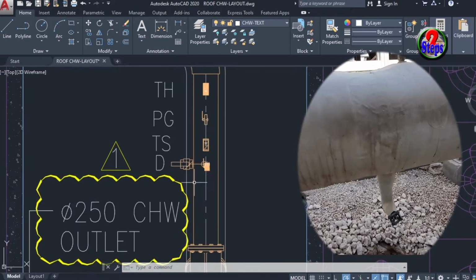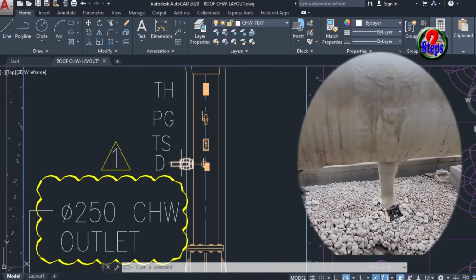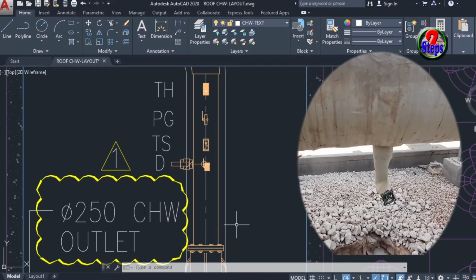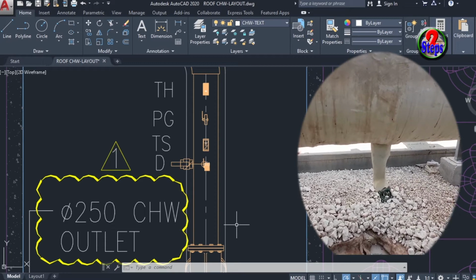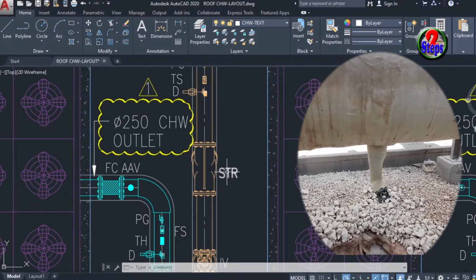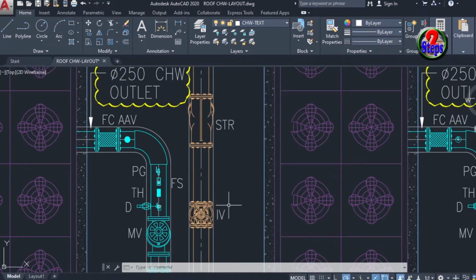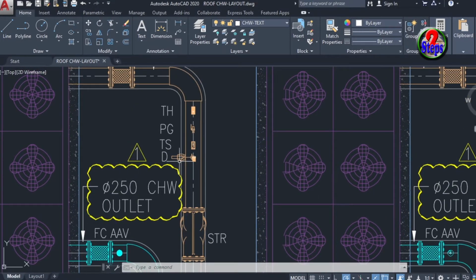Next point is the drain with a gate valve. The drawing symbol is D. It's installed at the bottom of the pipe. During unit maintenance, both the inlet and outlet isolation valves will be closed, and then the reserve water can be thrown out by the drain.